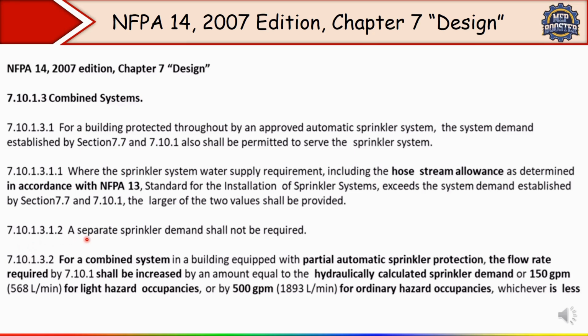Now the next point is separate sprinkler demand shall not be required here. It means if the system already accounts for the higher water demand, either from the standpipe or sprinkler, no separate sprinkler demand needs to be added here. Okay, and the most important point given here: for a combined system in a building equipped with partial automatic sprinkler protection. First you need to try to understand what partial automatic sprinkler actually is. See, partial sprinkler protection means that only certain areas of the building are covered by sprinklers rather than having a full sprinkler system throughout the entire building.